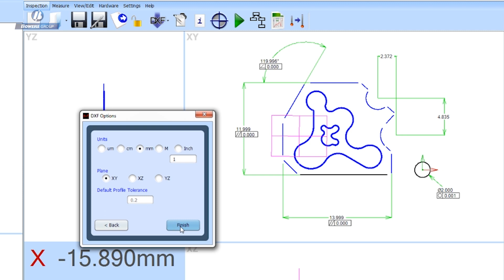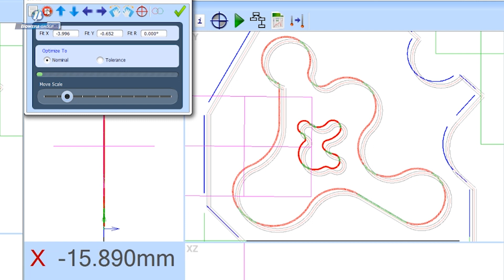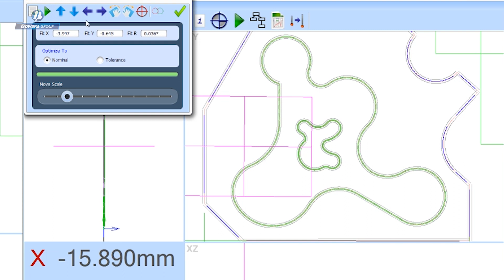Just like you would do with the profile projector, you'd manually move that overlay chart around to try and visually align that with the image. We can do that also using these controls. So I'm going to jog the DXF to the left, to the right, up and down, and I can also rotate it, but clearly what I want to happen is for the software to calculate the best fit. So by pressing the start button there, the software does a calculation and has mathematically fitted the DXF so that the profile error is actually minimized. This is the best profile error.